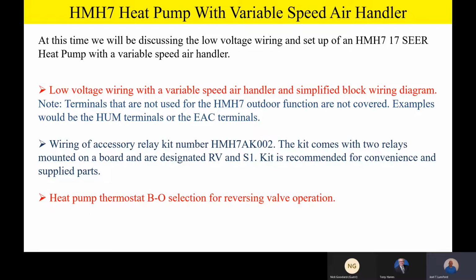What if you can't get a 002 kit? Oh my goodness, am I stuck? And the answer is absolutely not. All you would have to do, instead of having the 002 kit, is provide your own bi-flow filter dryer and then take two relays with 24-volt coils, single pole, double throw switching action. Mount those in the air handler, make up some field wiring, and you're going to be perfectly fine without the 002 kit.